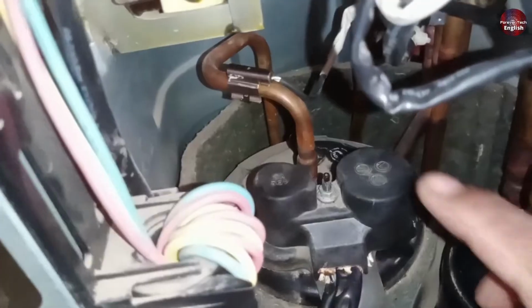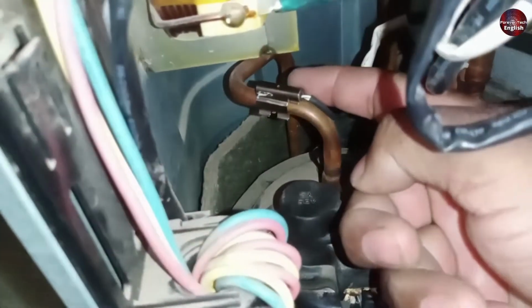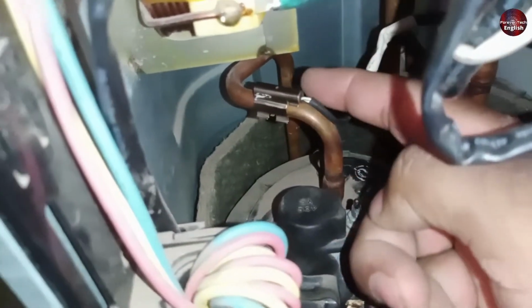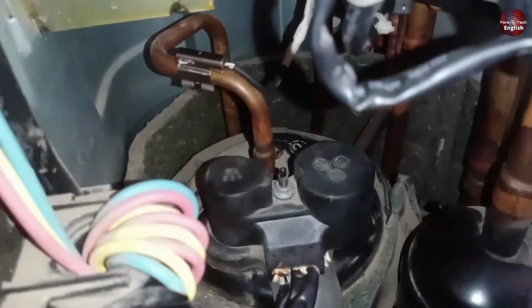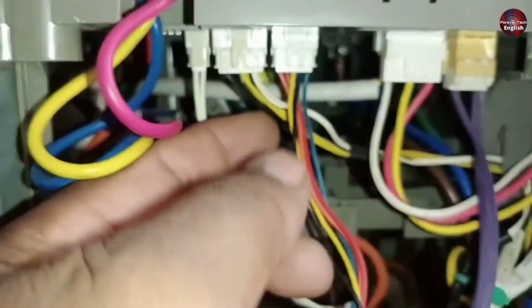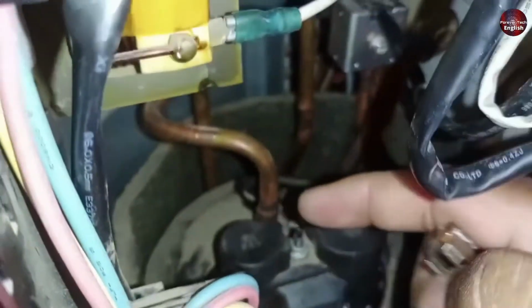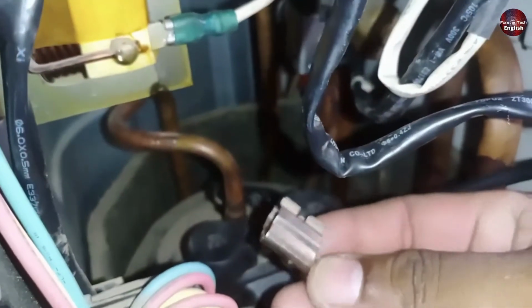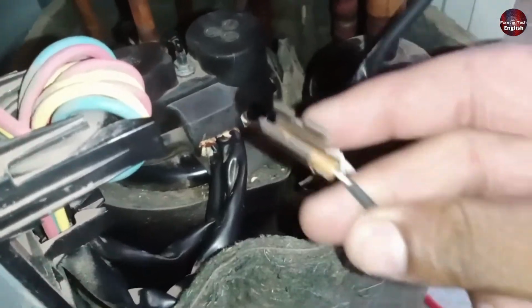Now, I will show you where it is located on the compressor. As you can see here, it's attached directly to the pipe that comes out from the top of the compressor. If this sensor becomes loose or disconnected for any reason, it will also trigger the F5 error code. Let me show you what this sensor looks like. Here, I've removed it, and as you can see, this is what it looks like. Whenever this sensor goes bad, the unit will display the F5 error code.